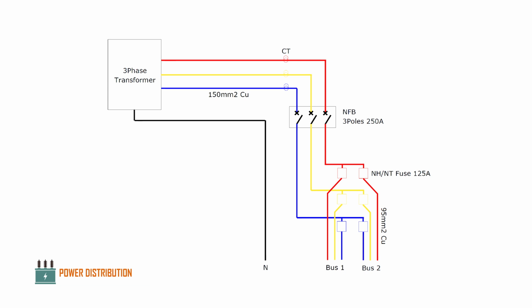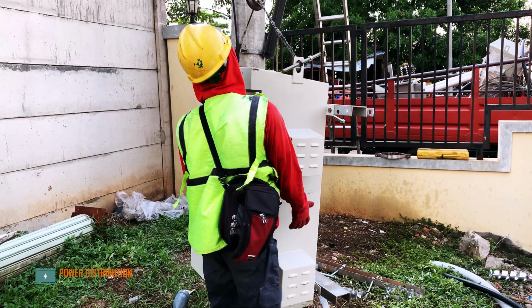Then the bus bar, which comes out from the NFB, is divided into two buses via 125 amperes NH or NT fuses for each phase. And last but not least, 95mm squared copper wires are connected to the fuse for each buses and acts as a secondary distribution conductor or wires to the consumer. Back to the installation video.